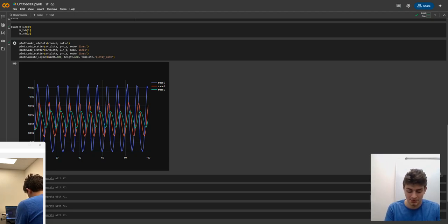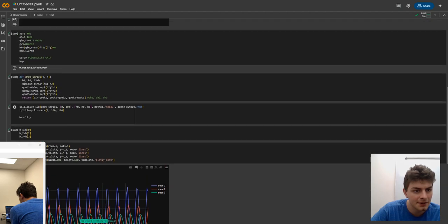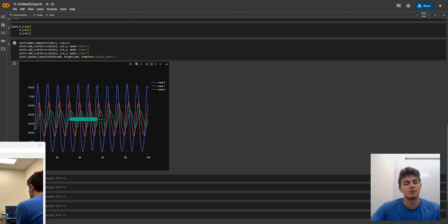Again, we're calling that value ultimate gain. And we'll talk about that later when we go into tuning. But this is kind of the ultimate gain for this system, right? You can see that if, you know, maybe we hit the exact middle of this system here, we'd have about 0.015. And again, that's what we're really looking for, is this value. It's kind of right in the middle of these oscillations. If I were to draw the line that might be like the 0 for this sinusoidal wave, it would be pretty close to our set point, right?